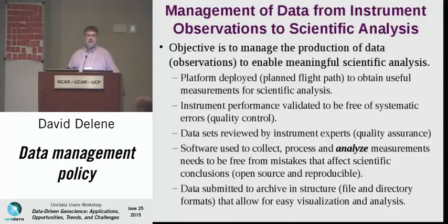So an expert has to review that data and make that determination. Is this data at all scientifically useful? If it's not, you have to replace that with a missing value code. The data has to be missing. And this is not like a quality flag. I just think, is it good enough for anything? And if it's not, you have to take that out. And these are things that I don't think can be automated. You can look for range checks and stuff, and you can automate that. But this is stuff where you really have to understand the science of the instrument, how it works.